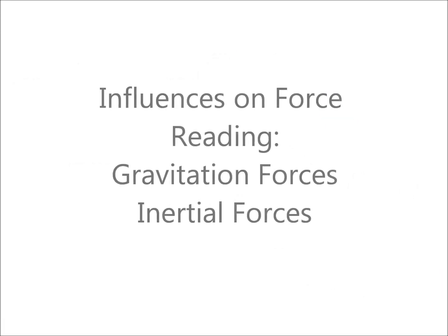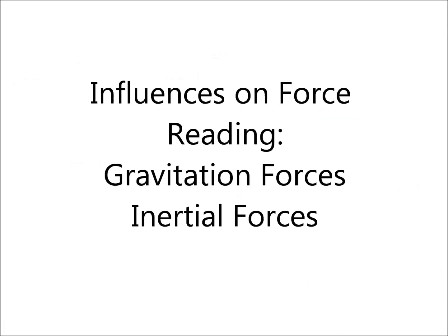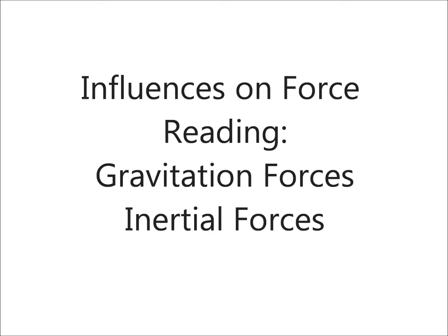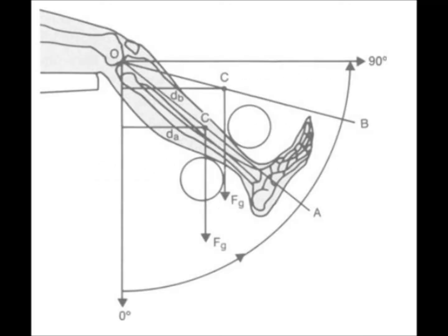Mathematical algorithms are also entered into the machine to account for the force produced by gravity and inertia acting on the limb. Since gravity is acting on the center of mass of the limb, the equation uses a differential equation that depends on the current angle, which is constantly changing throughout the exercise. As seen in this picture, the gravitational torque in position B will be larger than the torque in position A.